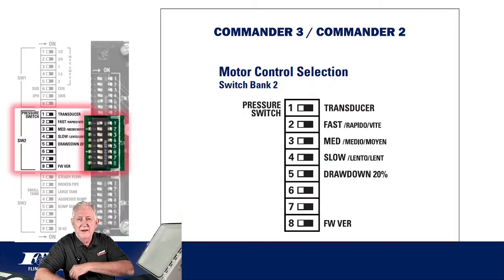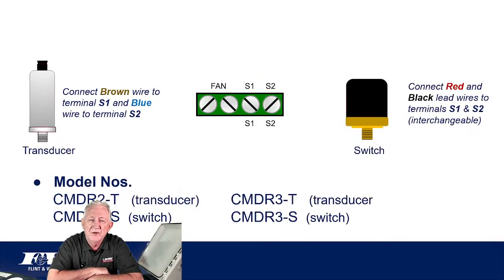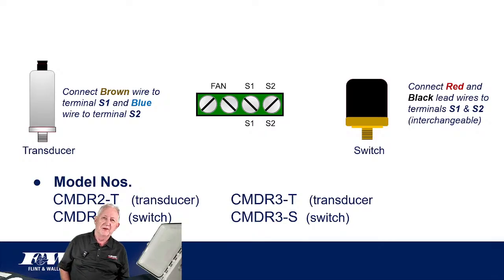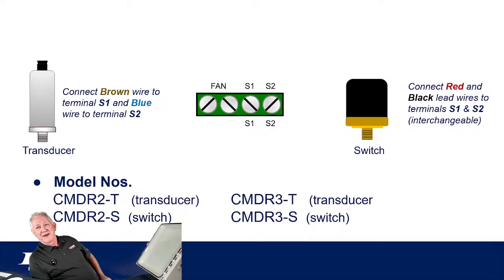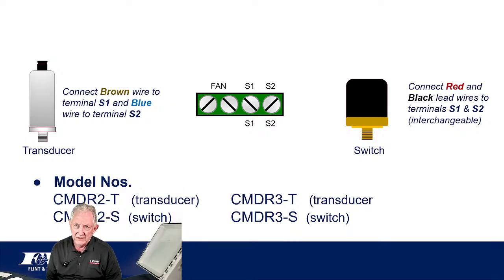All right, this next slide, let's see what we got here. So here's our transducer and our pressure switch, okay? Now, I'm going to move my head just out of the way a little bit. So here we go. With the Commander 2, that's a 2-wire drive. Based on the model number, CMD, Commander Drive 2, if you go with a suffix of -T, we'll ship that drive with a 100-pound pressure transducer. If you put an S suffix at the end of that model number, then we'll ship that drive with a pressure switch. And those two are indicated up there at the top of this slide.